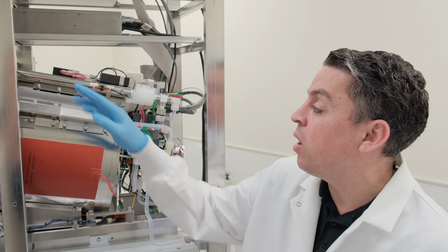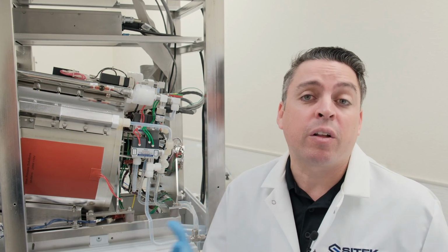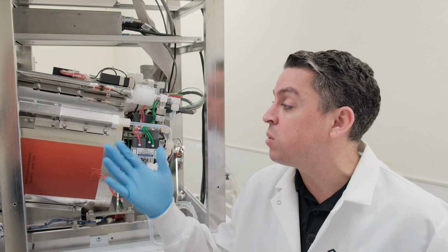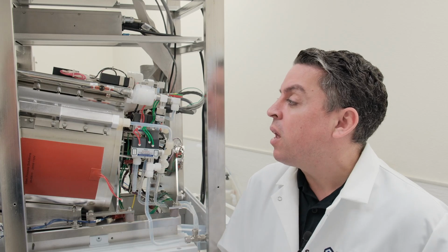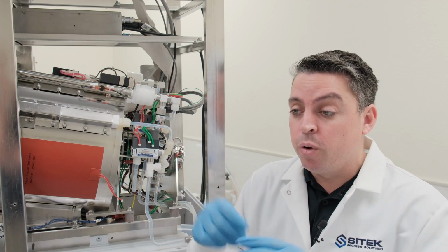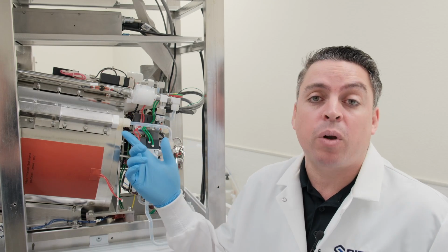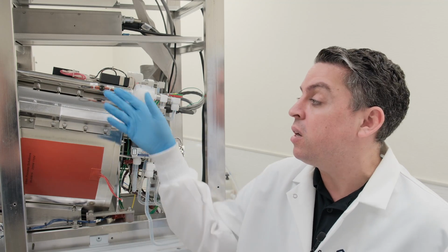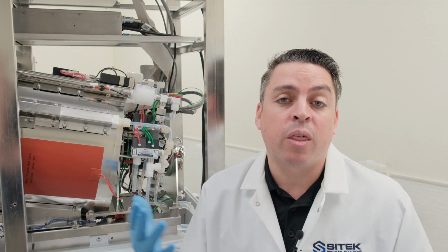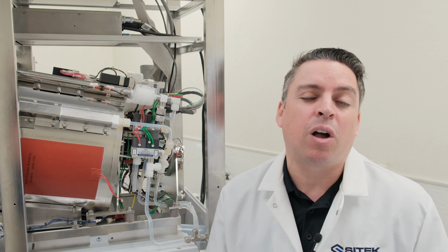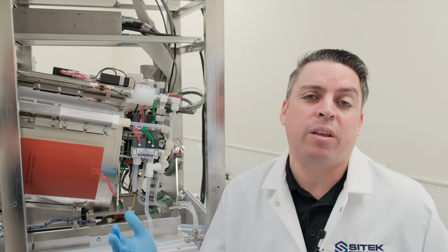The second uncommon cause is going to be the actual N2 heater itself failing. In general, heaters are fairly robust. You don't have a lot of problems with the actual heaters themselves. Normally, it's the sensors associated with them, and so that's why that's uncommon. However, if you do find that your heater's failed, when you remove it, you're going to see that it's damaged. At that moment, we want to investigate further to see if there's going to be any particle problems with our system, because when that N2 heater actually damages like that, then there's a chance that inside the manifold we have particle contamination or other issues. If that's the case, those are all still common services for us, and we can help you electropolish or replace your manifold and get your tool back into running condition quickly.